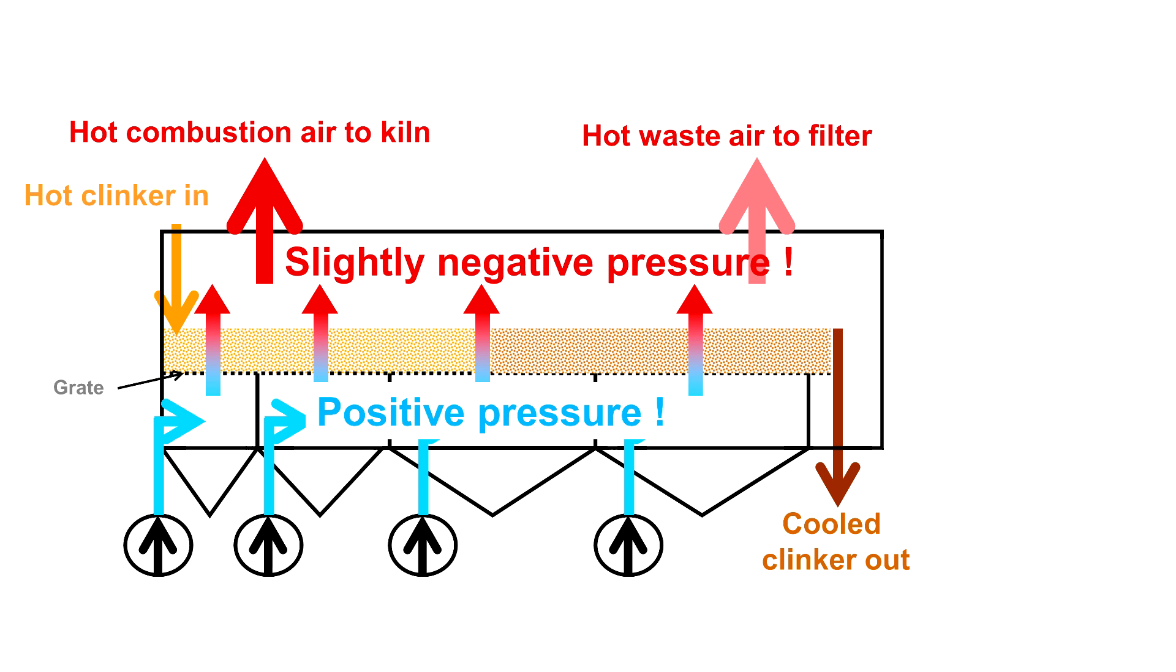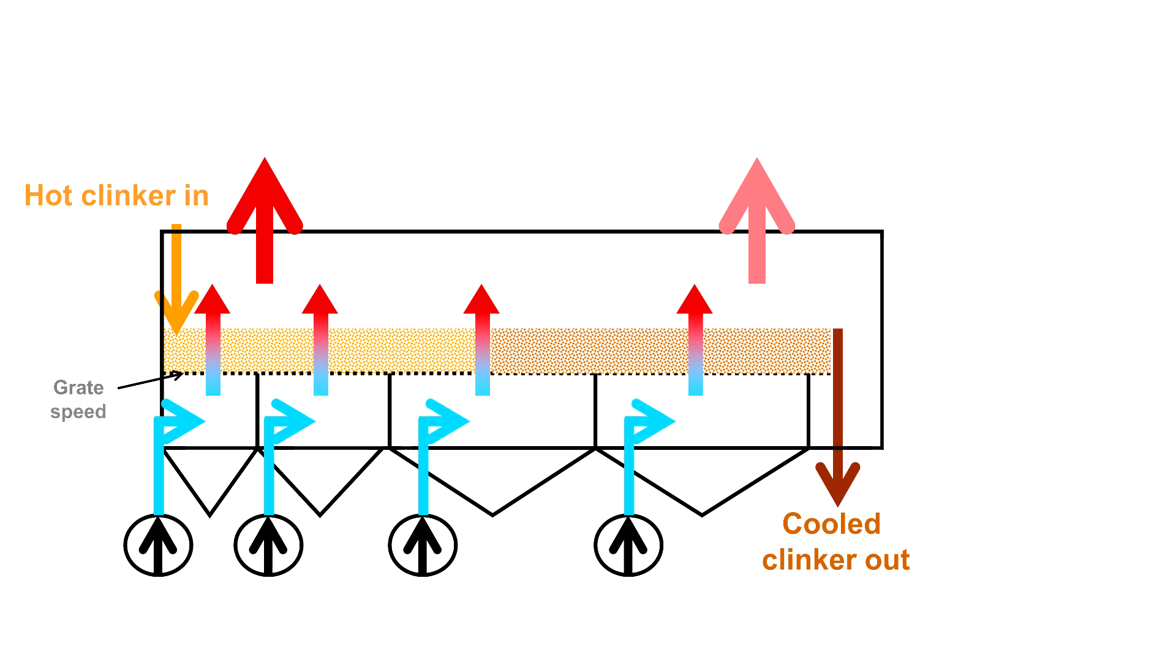There are two main reasons to keep a negative pressure on top of the grate: to avoid blowing clinker dust outside of the cooler, and to limit the intake of false air in the system. The clinker cooler has two main controls. First, the grate speed.